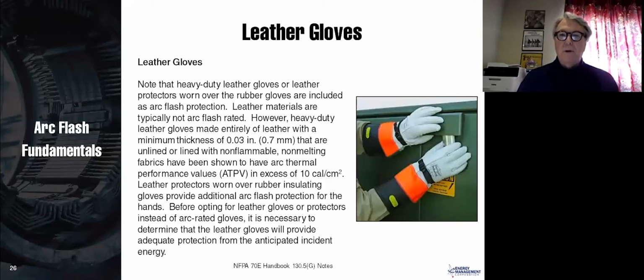However, heavy-duty leather gloves made entirely of leather with a minimum thickness of 0.03 inches that are unlined or lined with non-flammable, non-melting fabrics have been shown to have an arc thermal performance value in excess of 10 calories. So basically, for anything that is within that second group that goes from 1.2 to 12, for the most part, if we have the leather gloves, they're rated 10 calories, and then we have rubber gloves under those leather gloves, we're pretty much going to be good for 12, although this is kind of loose in the standard.